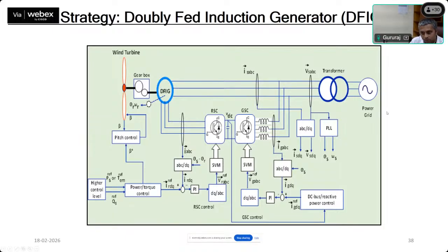The voltage dips, there is a DC transient of flux, rotor speed cannot change, and because of which a huge amount of voltage is induced on the rotor side, and an increased value of current will flow. The insulation material of the converters may blow off, or the converters' current carrying capability is limited, that may also blow off. And the most vulnerable point, which is the DC link capacitor, may also get damaged.